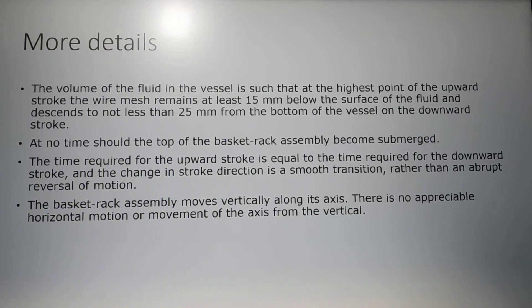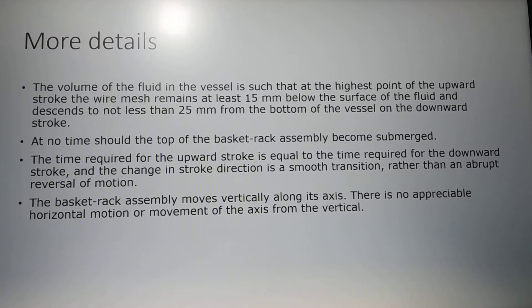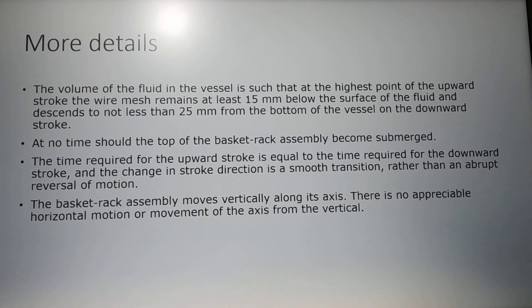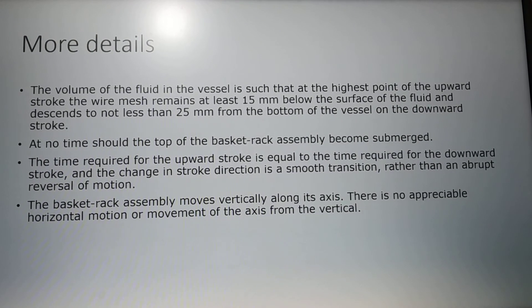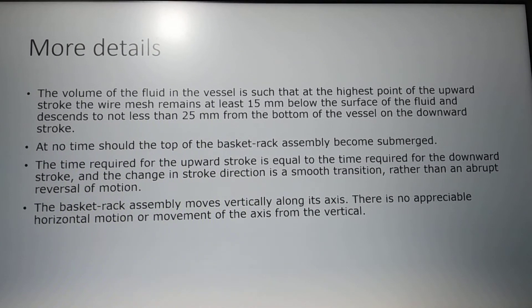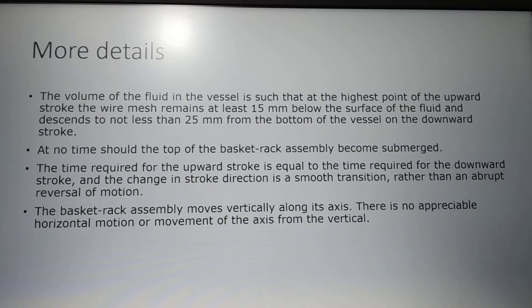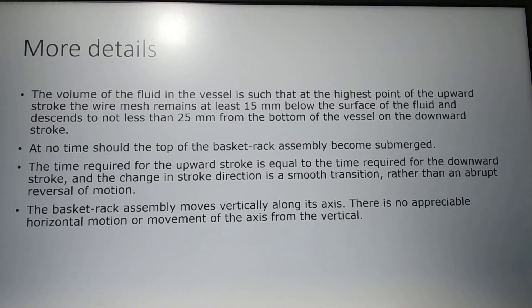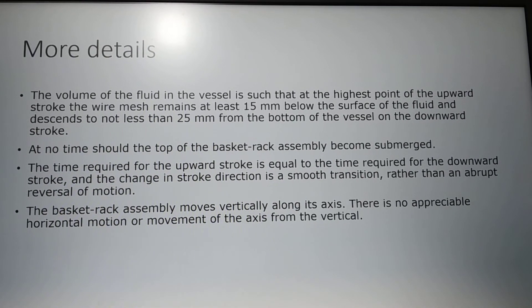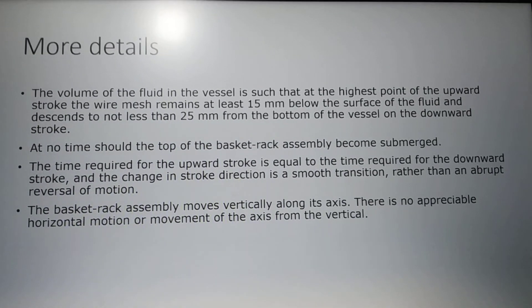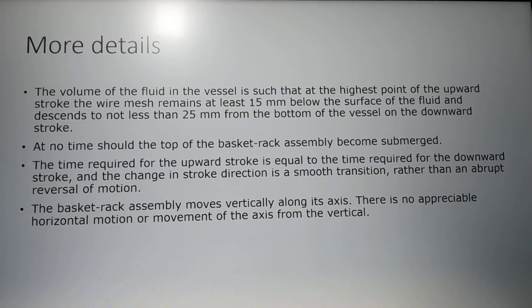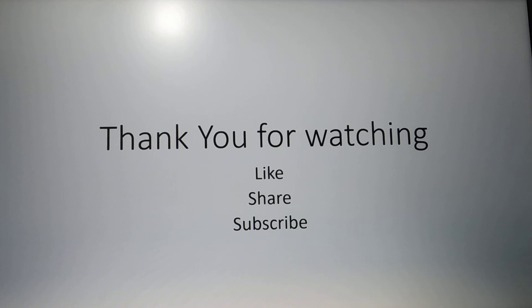The time required for the upward stroke and downward stroke should be equal, and the movement should be smooth — there should not be any jerking movement during the up and down movement of the basket. There should also be no horizontal movement of the basket; it should only move in the vertical direction. These were the details of the disintegration test apparatus.